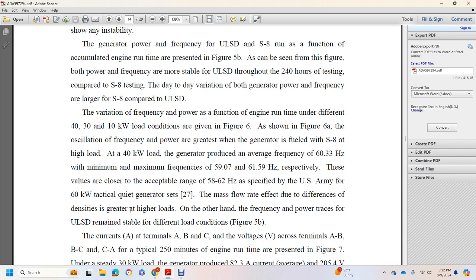As shown in figure 6a, oscillation in frequency and power is greatest when the generator is fueled with the S8 at the high load. At 40 kilowatt load, the generator produces an average frequency of 60.33 Hz, with minimum and maximum frequencies of 59.07 to 61.59 Hz respectively. These values are close to the acceptable range of 58 to 62 Hz as specified by the U.S. Army 60 kilowatt tactical quiet generator set, with the mass flow rate effect due to the difference in density greater at higher loads. On the other hand, the frequency and power trace of the ultra-low sulfur remains stable under the different load conditions.